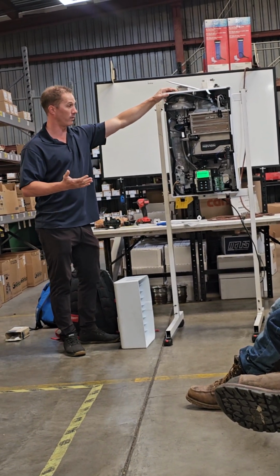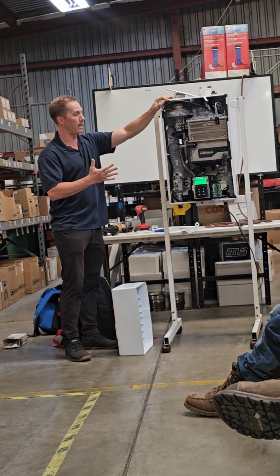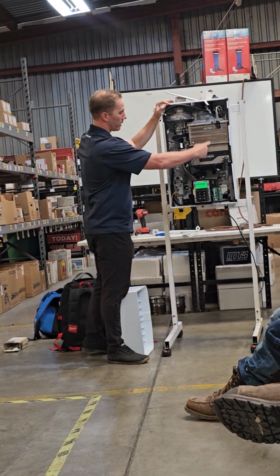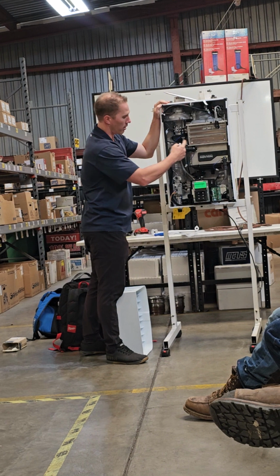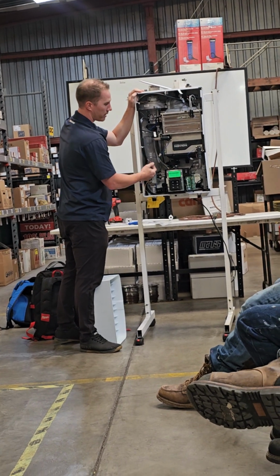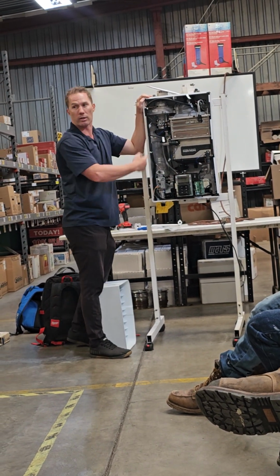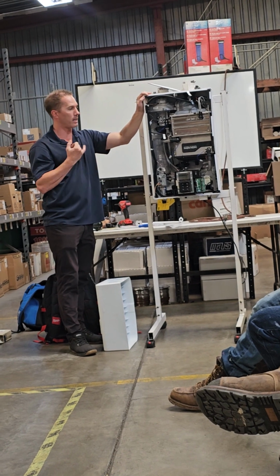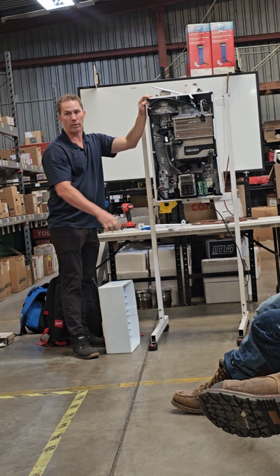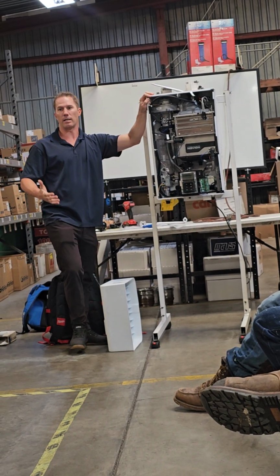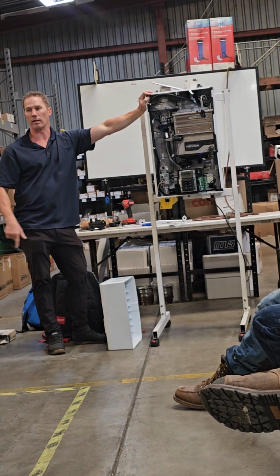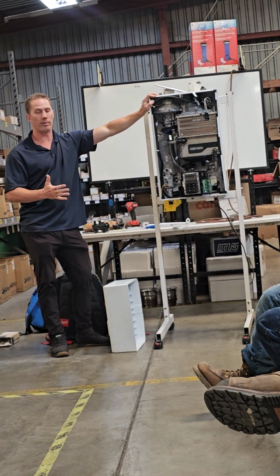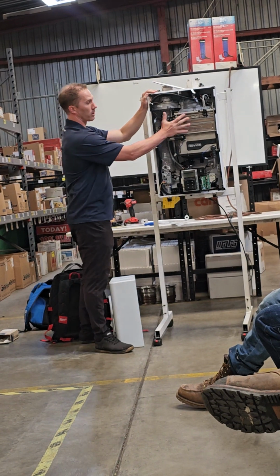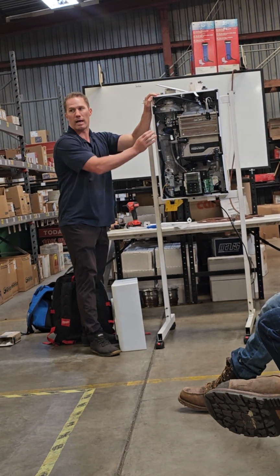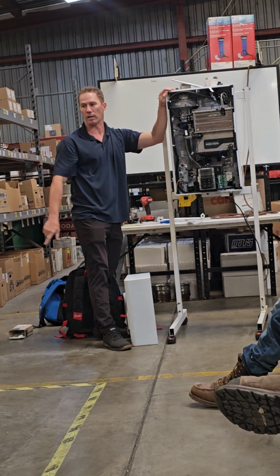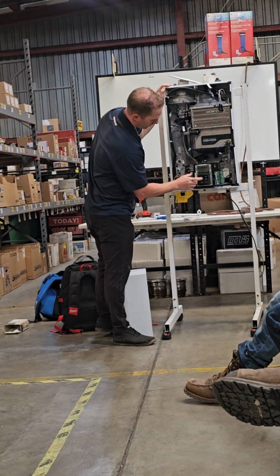This has gotten kind of confusing to some people. Internal means it's recirculating inside of itself, going from the heat exchanger to the buffer tank and back, just recirculating inside the unit. External means it's leaving the box and going into the house. A lot of guys think, oh, I put internal because it's going into the house, but that's wrong. Internal just recirculates inside the unit; external leaves the unit and goes into the house.